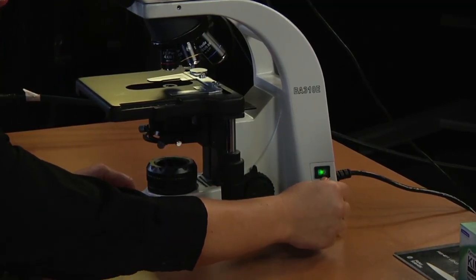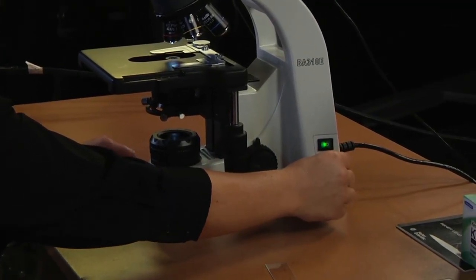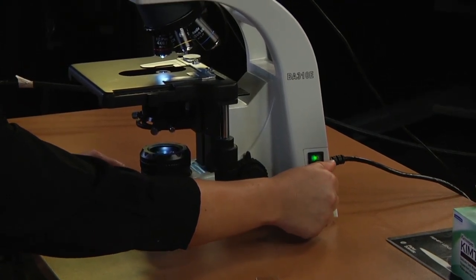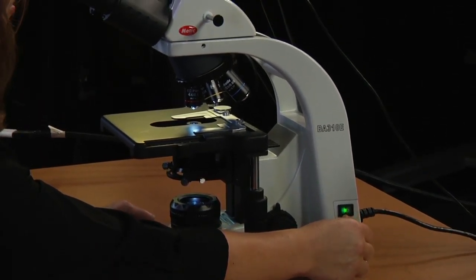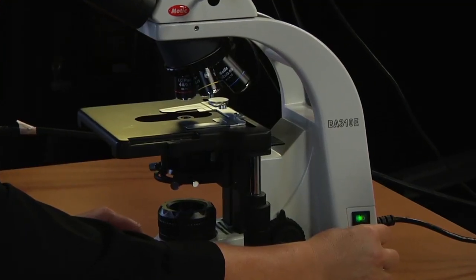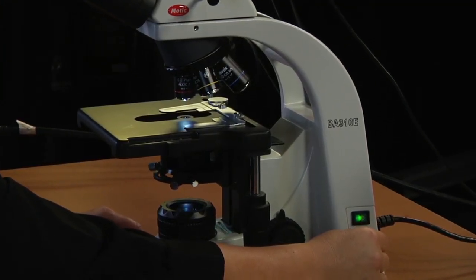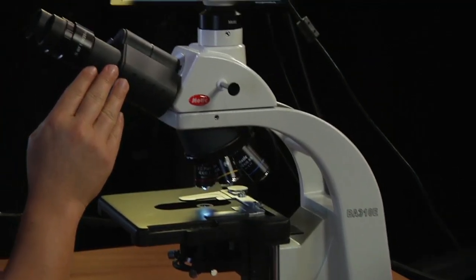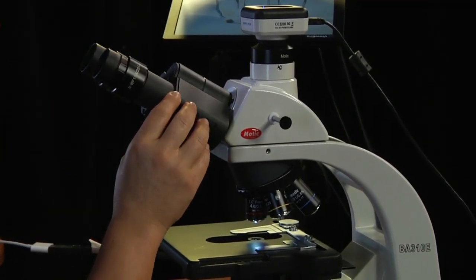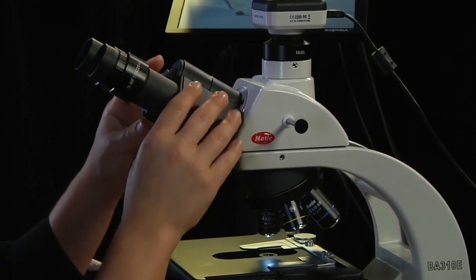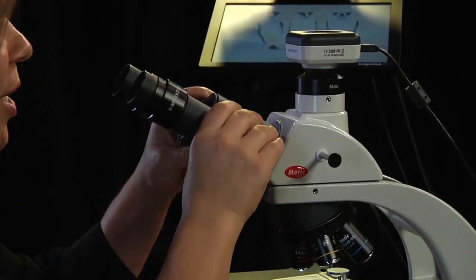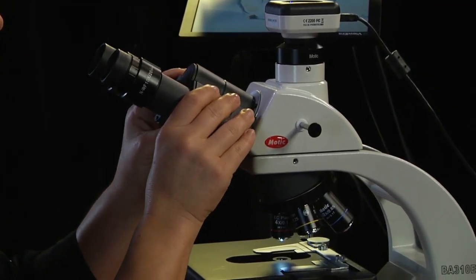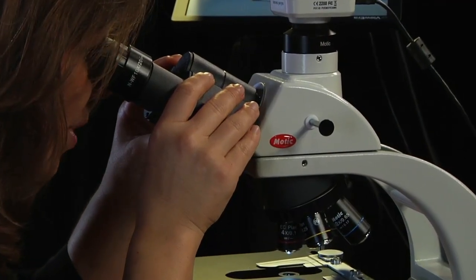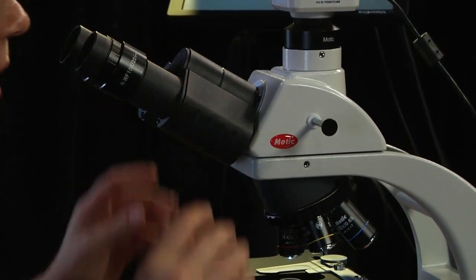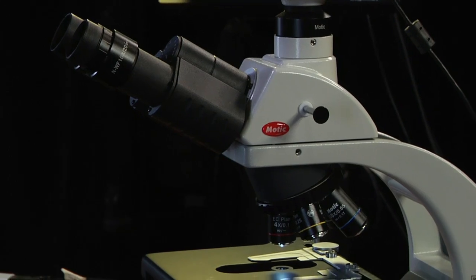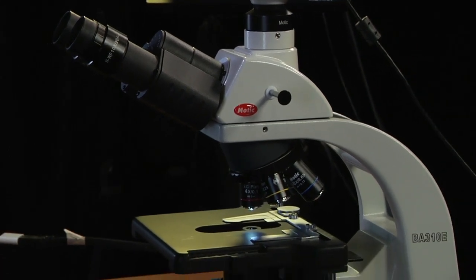The dial underneath the on-off button lets you increase and decrease the light intensity. Turning it back increases the light intensity, turning it to the front reduces the light intensity. You want to make sure that your eyepieces are set for your eye distance. Every person has a different distance between their eyes, so you can adjust the eyepieces to fit the distance between your eyes. Always use two eyes to use the microscope. It's a binocular, which means for your two eyes.